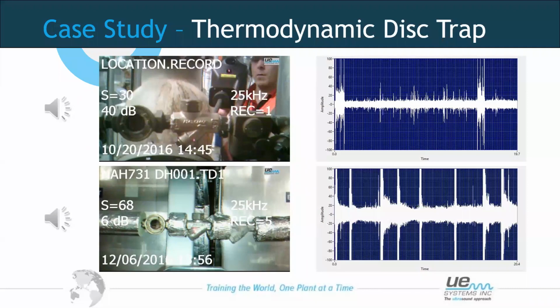So, with steam traps, as you can see, we can identify the condition. We can compare like for like traps. Okay, so as you can see from this one, we see the ideal steam trap, and in the second recording, we can see one now lacking efficiency. And sometimes, especially with thermodynamic disc traps, a common problem, because it's such a harsh movement of the disc inside, it can cause erosion on the actual disc itself. And then that means that it doesn't make a perfect seal. And in that respect, we'll also hear it chattering away, you could say. So this trap, for example, on the second recording is getting close to that point because it's opening and closing so much.